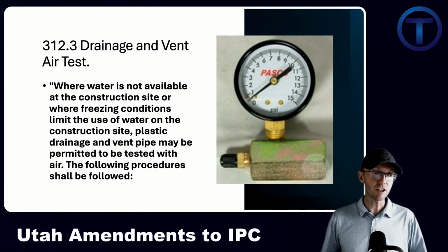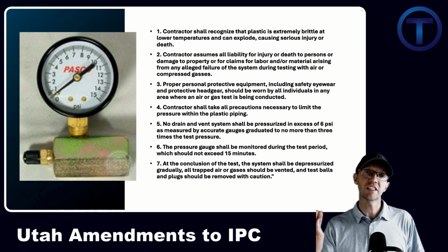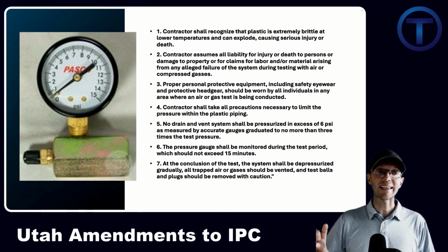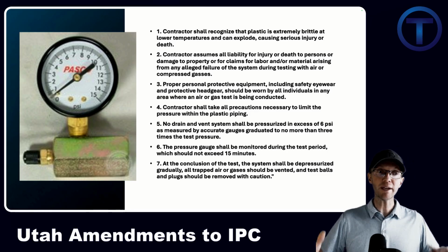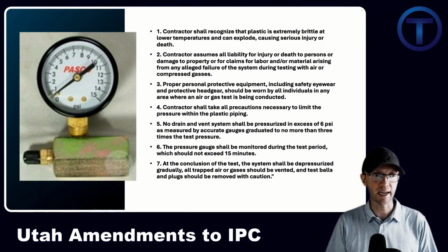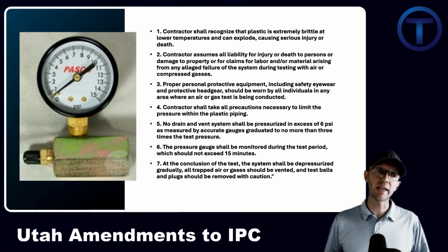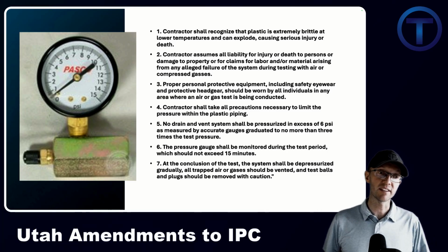The following procedures shall be followed. These are the things you need to know if you're going to test using air. First of all, the contractor shall recognize that the plastic is extremely brittle at low temperatures and can explode, causing serious injury or death. Please know you're in danger. Number 2, contractor assumes all liability for injury or death to persons or damage to property, or for claims for labor and or material arising from any alleged failure of the system during testing with air or compressed gases.